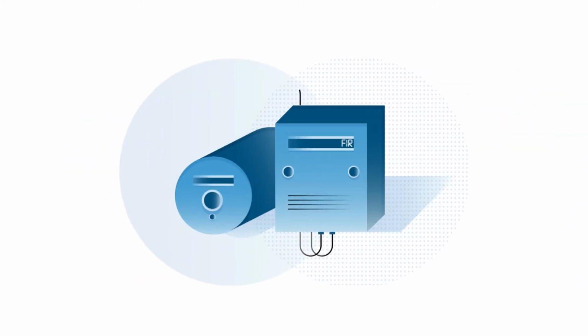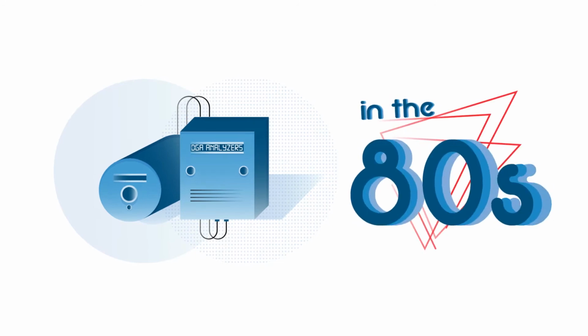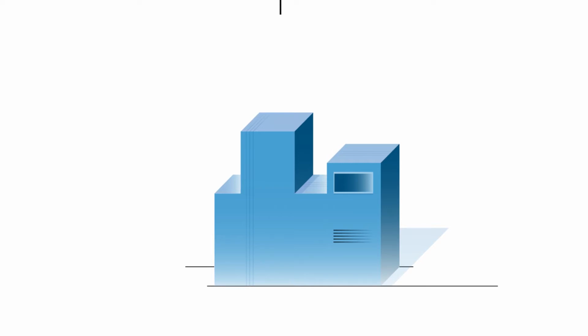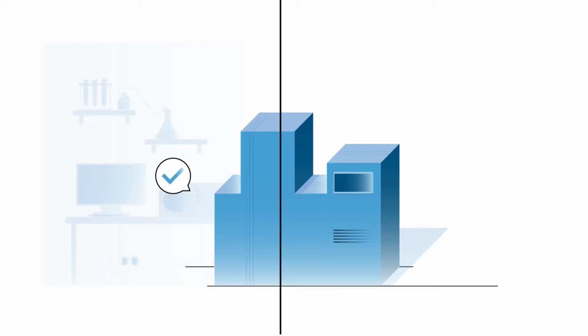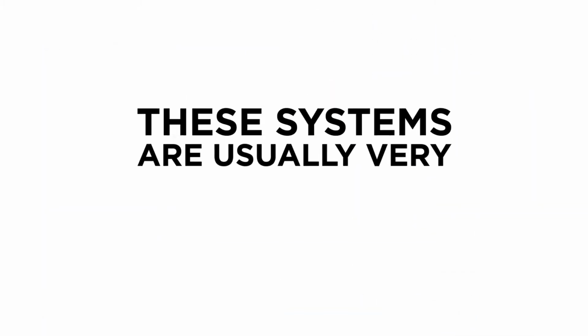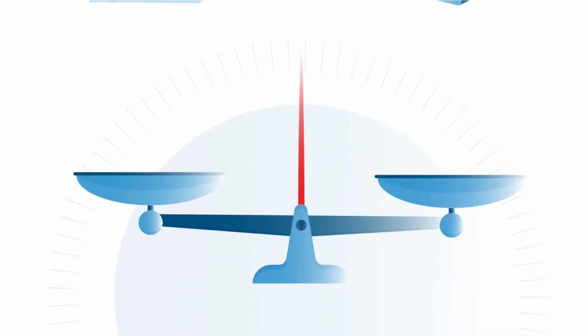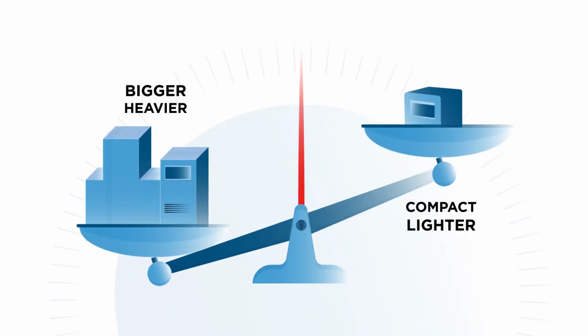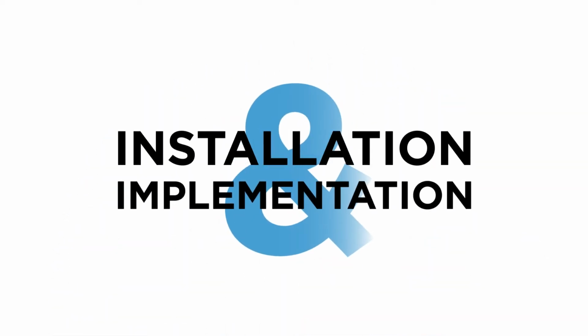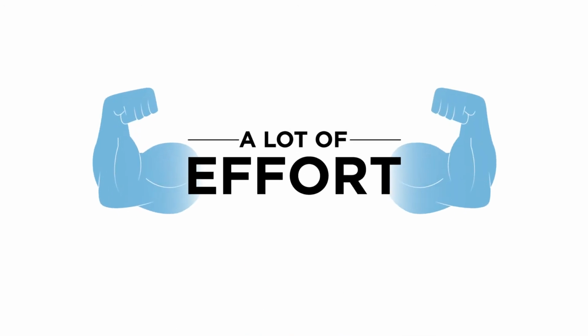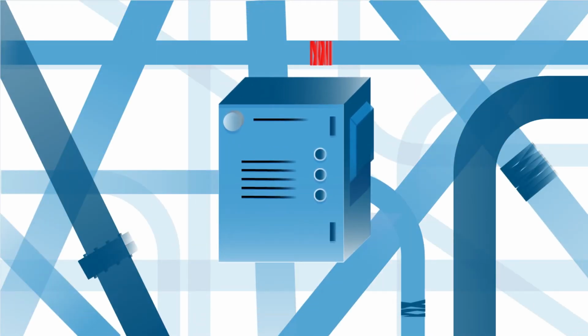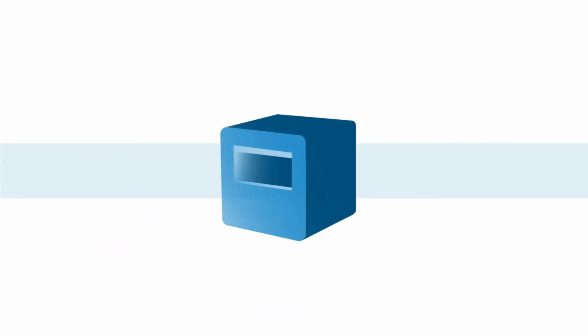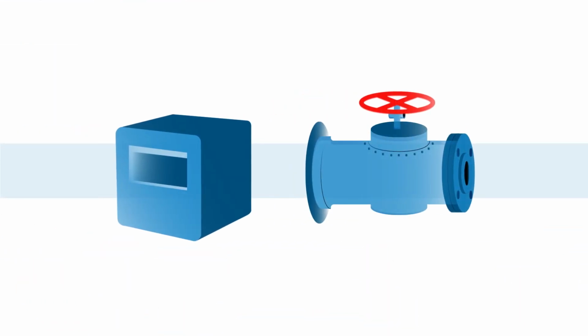The first online DGA analyzers appeared in the 80s. Up to now, most multi-gas systems with more than 2 gases have been based on laboratory gas chromatography technologies and have not been developed for real on-site applications. These systems are usually very large, unlike MTE HYDROCAL devices, which are compact and lightweight in their design. The installation and implementation of such systems also usually requires a lot of effort. The installation is indirect via piping, unlike MTE HYDROCAL devices, which are directly installed on the transformer valve.